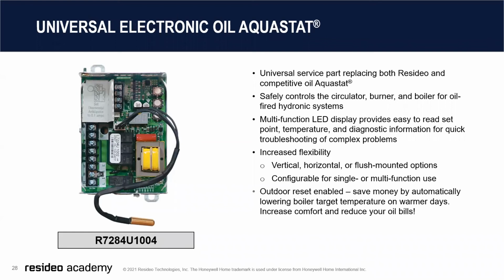The Universal Electronic Oil AQUASTAT. Universal service part replacing both Resideo and competitive oil AQUASTATs. I do get asked occasionally on the line if this is only for oil, and the answer always back is that it's 120 volts output for the burner, and typically that's the voltage you associate with oil, not with gas. Can it be used to work in a non-120? Yep, you just have to get relays and or transformers involved to make sure everything's done safely and you don't fry the burner. But it's typically used in oil applications.